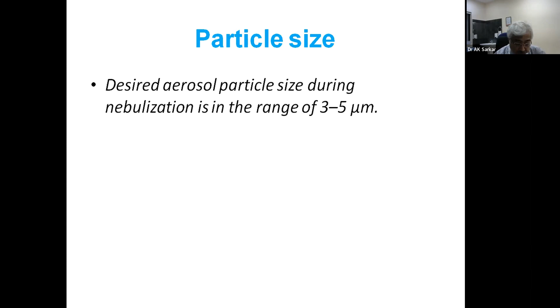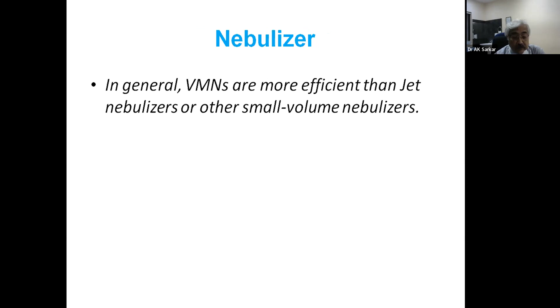And the best nebulizer perhaps is the vibrating mesh, because it generates a small size particle. A small volume can be used, the duration of nebulization is less, it doesn't interfere with the ventilator settings, and also you can use any solutions through this mesh nebulizer.